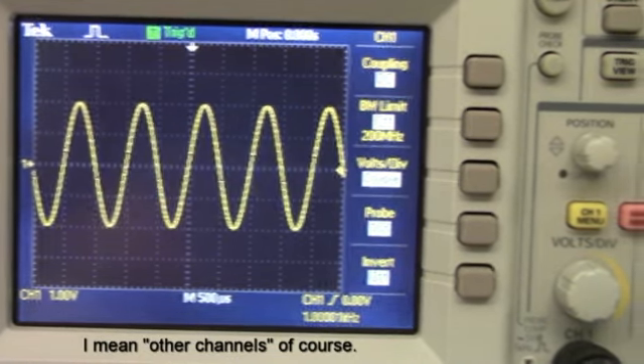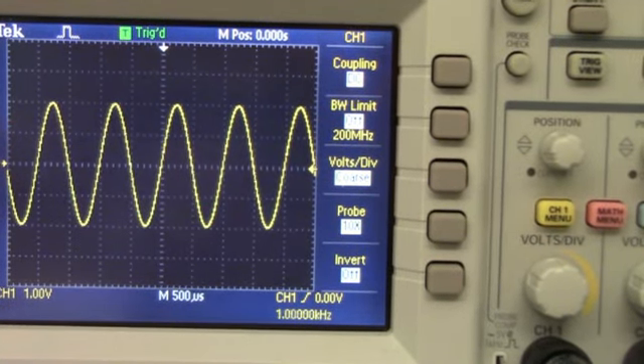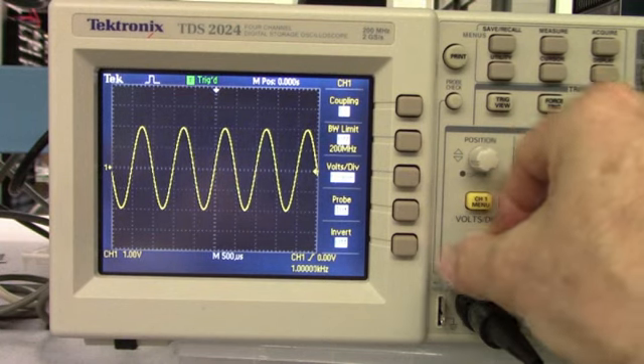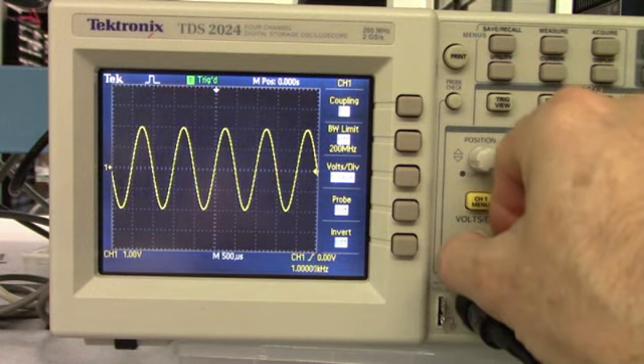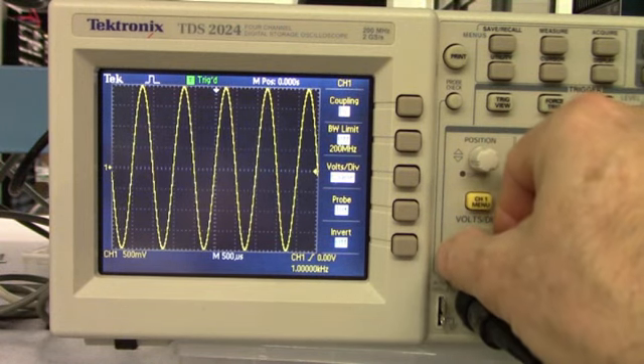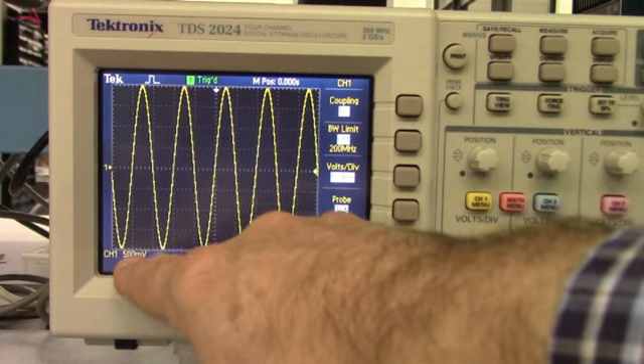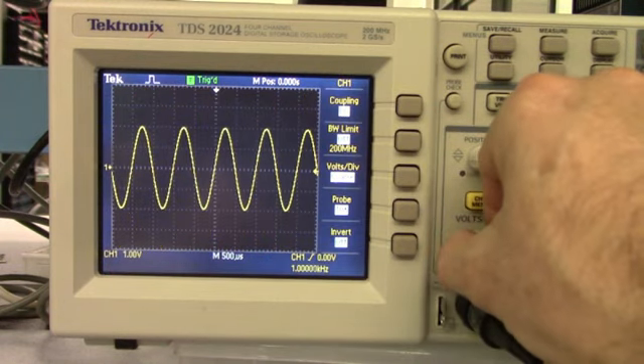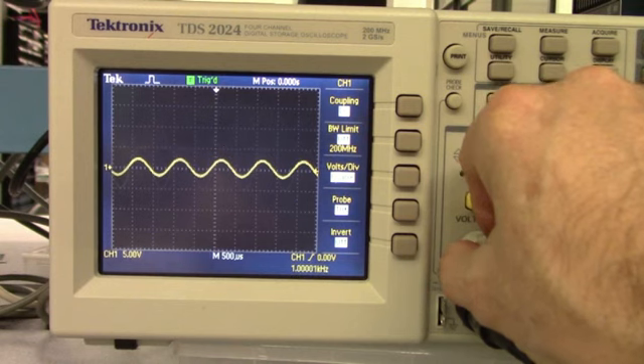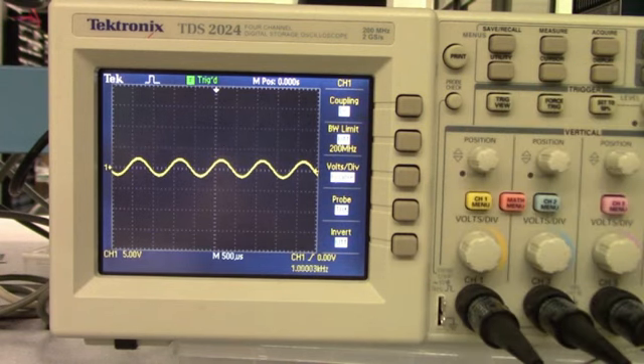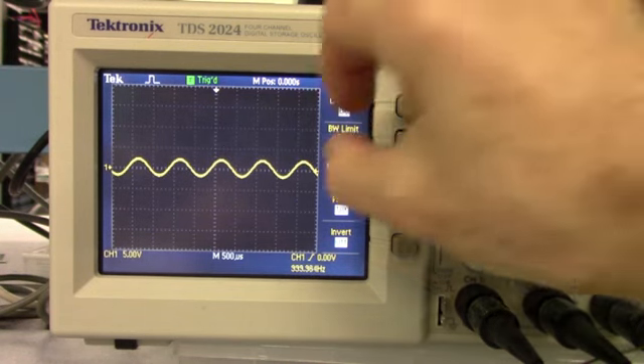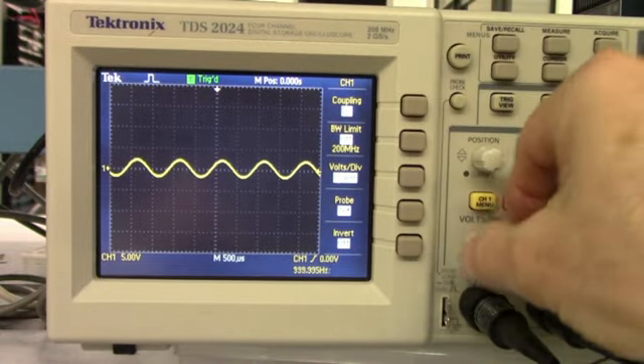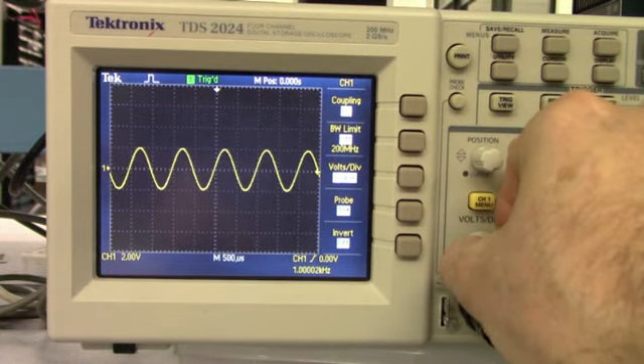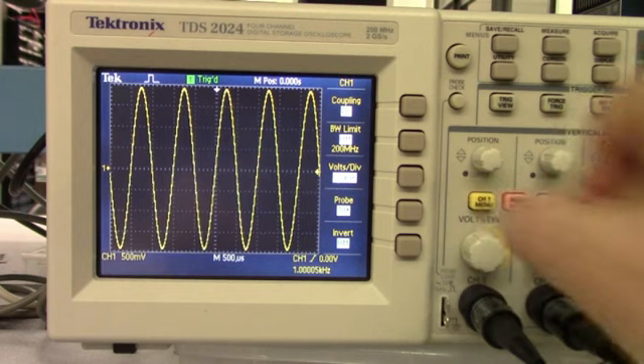So if we want to change the vertical resolution here, we can get the scale, we can go to a more sensitive scale. Instead of 1 volt per division, we're now at 500 millivolts per division. That makes our signal bigger, or we can go smaller. Now in general, we don't want to do this. We use visual measurements for the most part on the scope, and if we make the signal small, we're just wasting lots of screen.